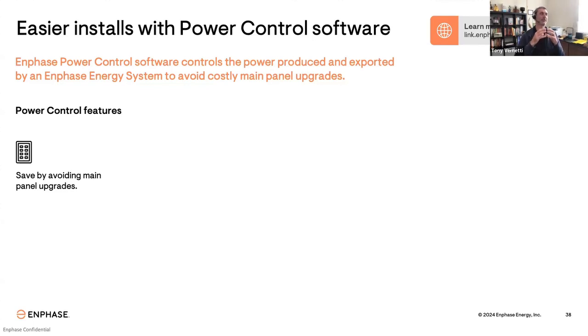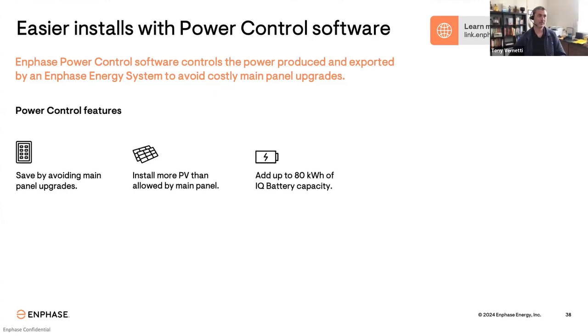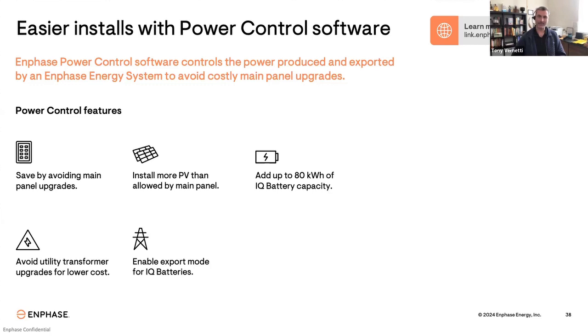So Enphase Power Control basically controls the power produced and exported by an Enphase energy system. And one of the key benefits is to avoid expensive main panel upgrades. It also allows us to install more PV than would normally be allowed by the main panel. It's used when we want to add all the way up to 80 kilowatt hours of battery capacity to our system controller. It can also avoid utility transformer upgrades. It's used to enable export mode for IQ batteries. Again, this is for those Californians that want to be able to export battery energy back to the grid. PCS also applies for that. And therefore maximize savings for those homeowners by exporting stored energy.